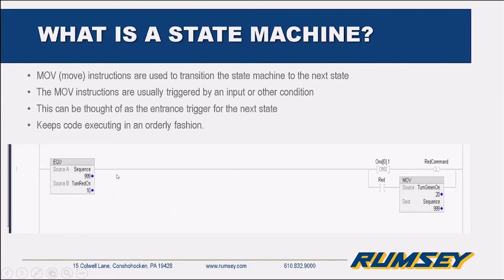Obviously, the equal statement allows the rung to execute. The move statement would be getting me out of the rung. In this case, I'm in. Now, granted, the state was not matching, so this code would not actually execute, but if it did match, if the sequence was 10 and it matched to 10, I would turn on something and then I would wait for the reaction, move on to the next state.